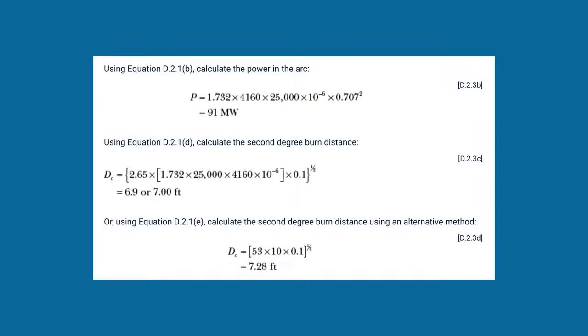Now, for the second degree burn, 2.65 is a constant, and you have the exact same thing going across except for one portion. You multiply by 0.1, and then take it to the half power, which gives you 6.9. That's not a cal rating but your distance, so 6.9 is your arc flash boundary.